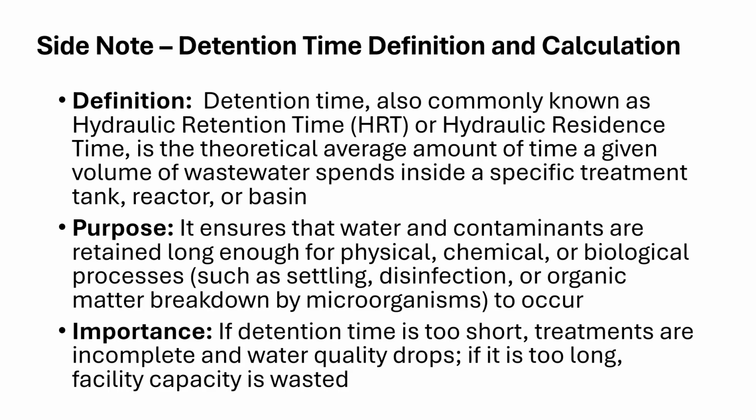That's basically the average amount of time that a volume of wastewater, whether it's a drop or a gallon or a bucket, is going to spend inside a specific portion or treatment process. In this case, a clarifier, or a tank or reactor or a basin. In this case, like I said, it's the clarifier.